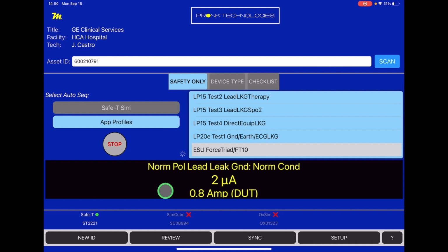So again, you can see on the safety analyzer here, on the Mobilize app, it's doing the testing necessary. We're now doing a lead leakage to ground test with open ground, and it's getting that measured value here. As it's doing each individual test, the information is coming back, being captured, so that it can all be in the electronic report, which we'll see at the end of the test. So it's important to make sure we're following the manufacturer's procedure. That's why it's helpful to have it programmed into the app so that there's consistency in what tests are being performed and all the leakage measurements that need to be captured.